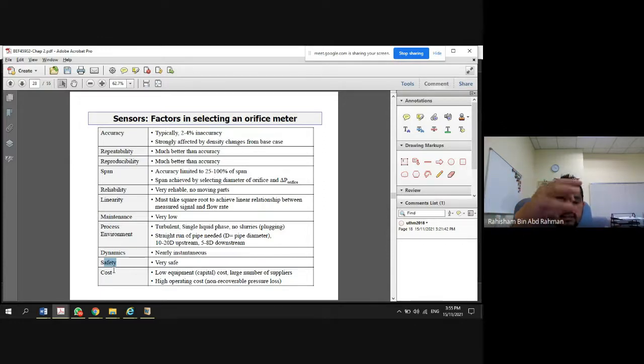It means that one device costs you about 100 ringgit, compared to one that costs 100,000 ringgit. The one with 100,000 ringgit has an accuracy of 2%, but the one with 100 ringgit has an accuracy of 5%. So as an engineer, we need to consider which one to give priority to. It depends on the application. If the application really needs accuracy, like it or not, you have to spend more. And if you can tolerate the accuracy, then you can go for the cheap one.